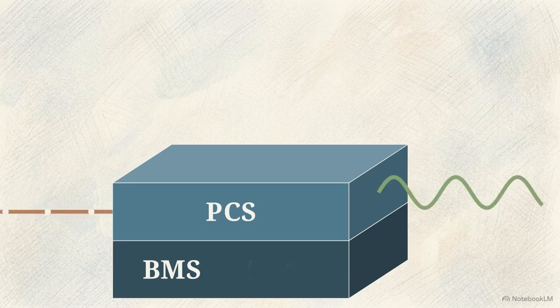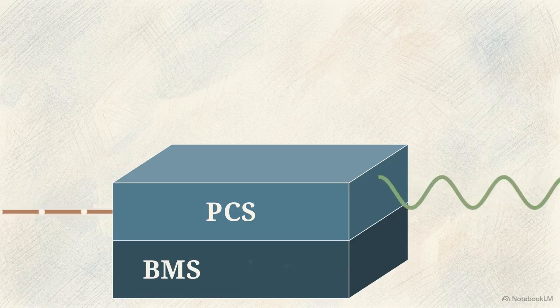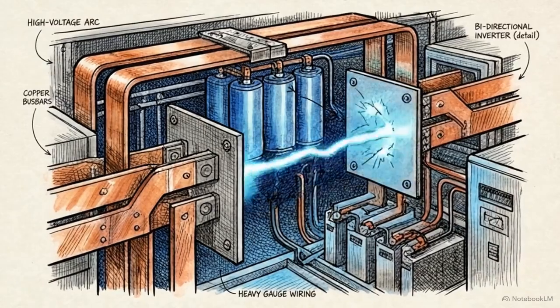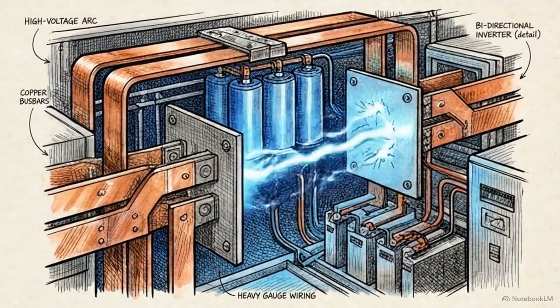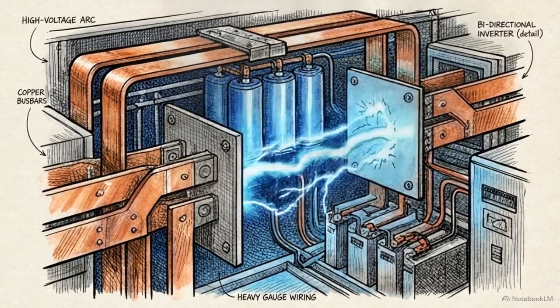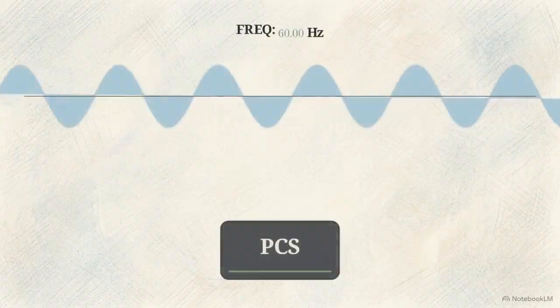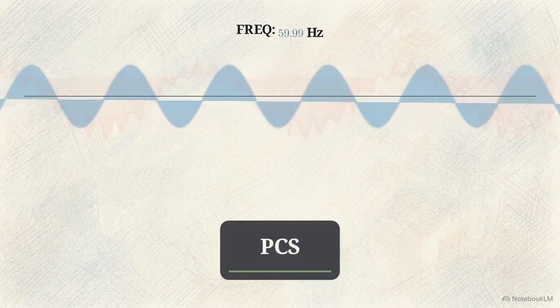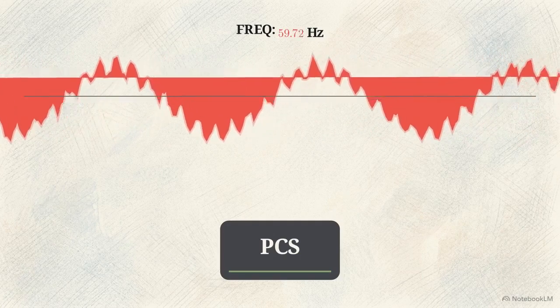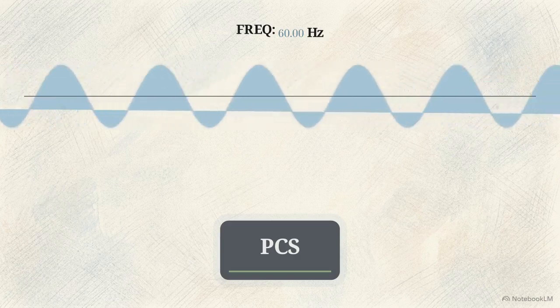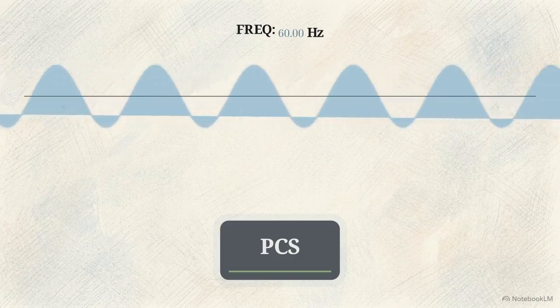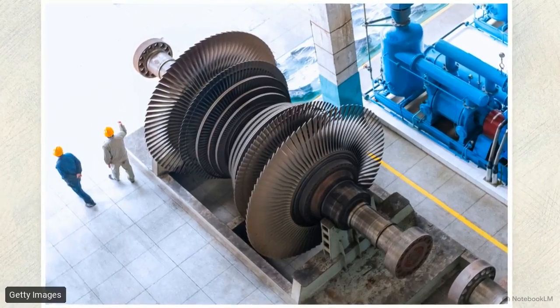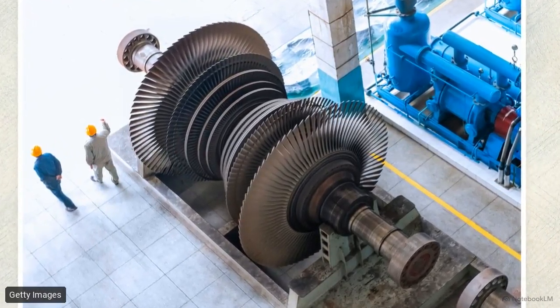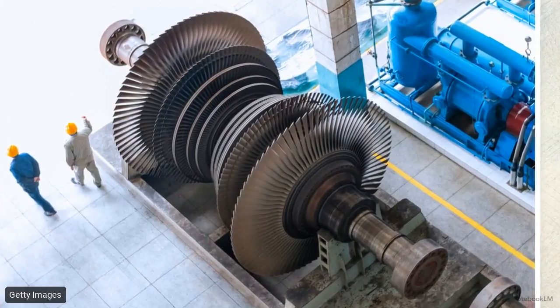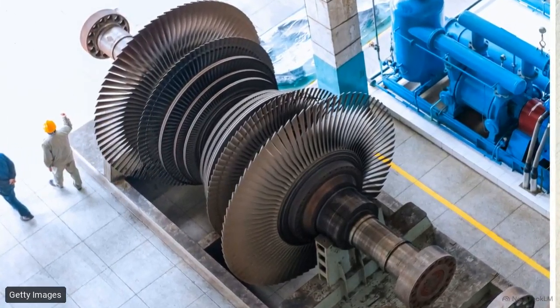This contains the crucial bidirectional inverters that bridge the DC power of the batteries to the AC power of the grid. This is where raw direct current is rapidly toggled and shifted to match the high-voltage alternating current required by local transmission lines. Operating on the grid, the PCS acts as synthetic inertia. It can inject massive amounts of AC power in milliseconds to correct dangerous micro-deviations in frequency. This millisecond response time stands in stark contrast to traditional spinning reserves or automatic generation control, which require minutes to physically throttle up generation.